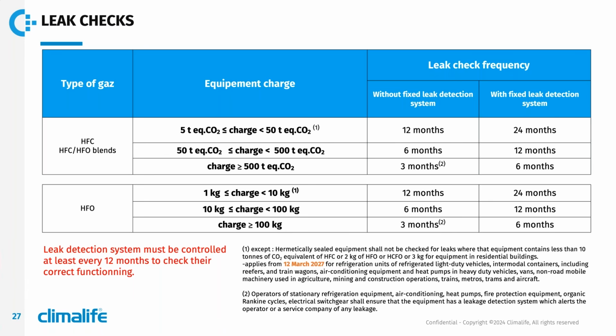Good to know: the indirect leak detection systems must be checked at least once every 12 months to ensure that they are working properly. And to finish, the last important point: in the event of a leak in a system, you have to repair it and check that the leak has been eliminated. But you should also carry out a leak test between 24 hours and 30 days after the repair.